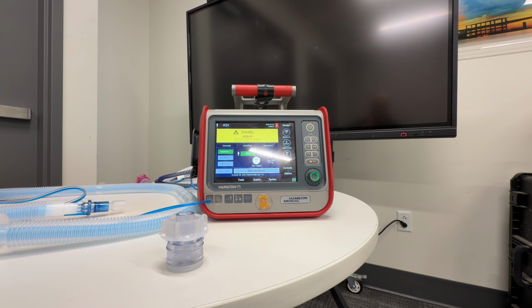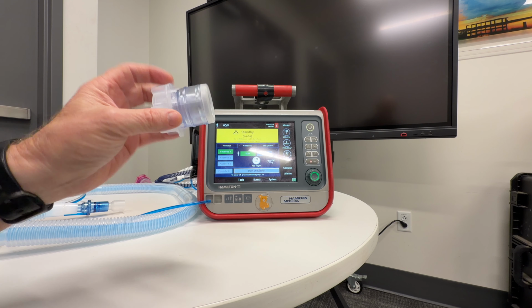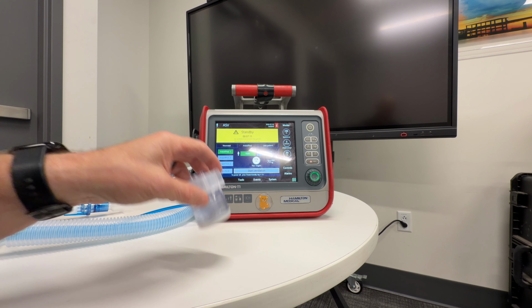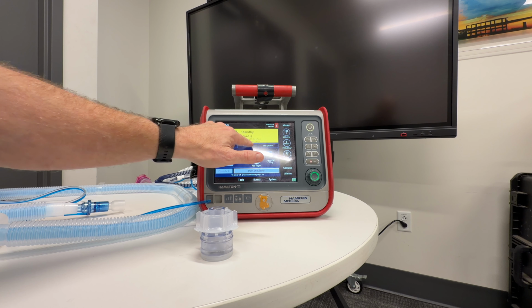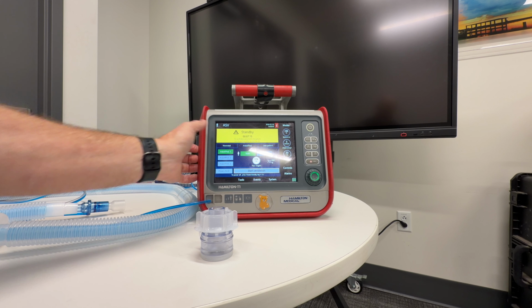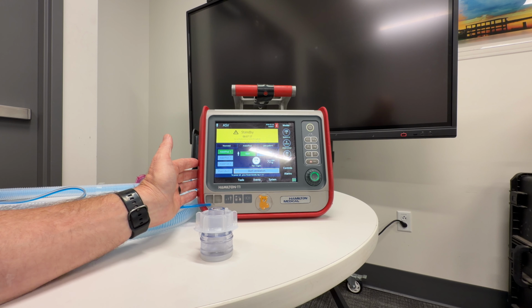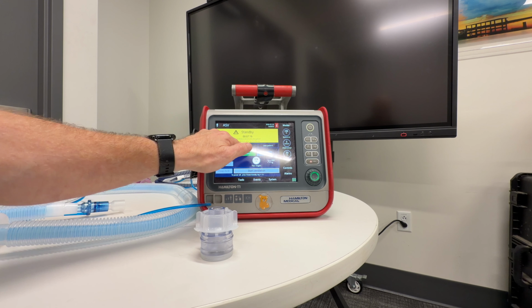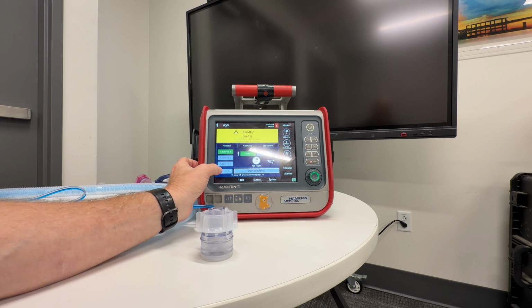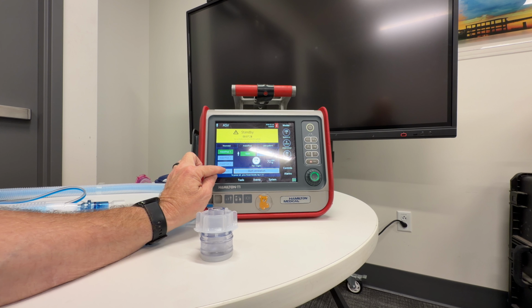So we're going to say that you just powered up your ventilator and you're going to do a pre-op check. One of the first things you want to notice is that if you're doing a flow test on an adult circuit, you want to make sure that this adult/peds is selected. Otherwise, if you select neonate, it's going to sense that you've got the wrong flow sensor. So we've got adult selected, and we're going to go down here and go to pre-op check.